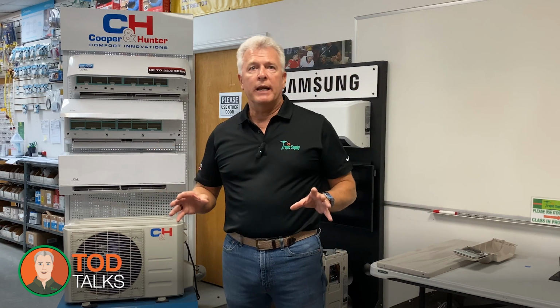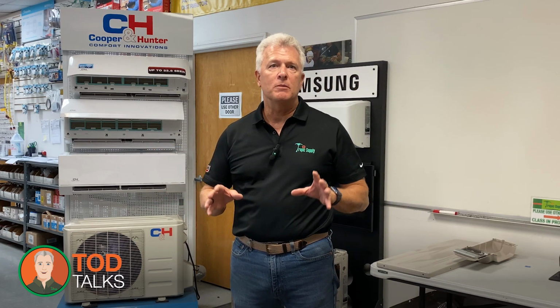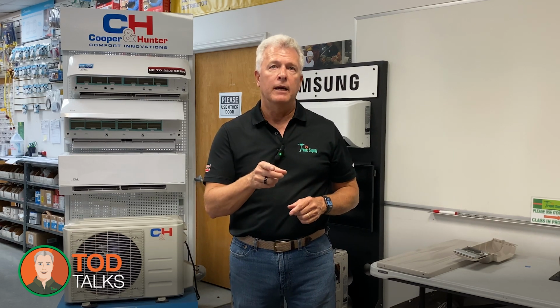Now here's an important tip. Mini splits are all about precision, especially when it comes to charging them. These systems are classified as critical charge, meaning you need to charge them by weight. This is different from the usual methods like measuring superheat or subcooling. You'll want to follow the manufacturer's spec to the letter, especially if your line set's longer than standard. Get this right, and you're well on your way to success.